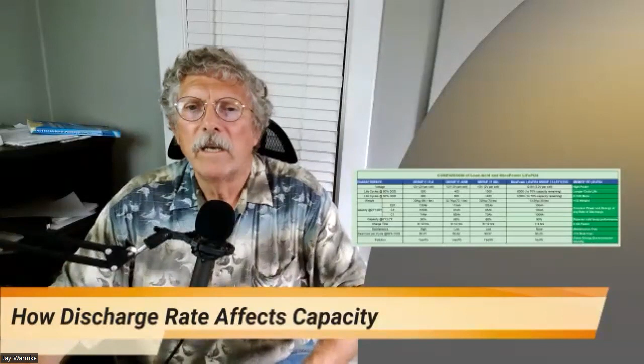For example, the comparison of what is the amp hour capacity: if we go to the middle of the diagram where it says C20 - and here they didn't put the slash in, which leads to some of my confusion - it's saying that in this first battery, there's 130 amp hours of capacity if you discharge it over 20 hours. It has 105 amp hours of capacity if you discharge it over 5 hours, and only 74 amp hours of capacity if you discharge it over 1 hour, from full to empty. So think about it like driving your car: if you're driving 100 miles an hour, you're going to get less gas mileage than if you're driving 30 miles an hour. It's the same car, same gas, just less efficient at a faster rate.